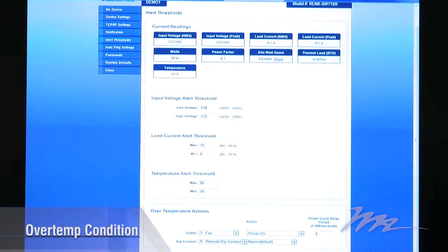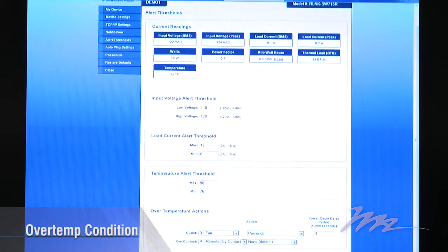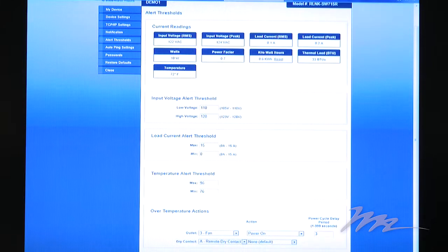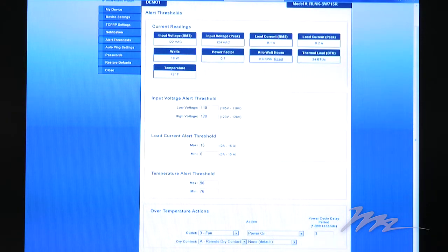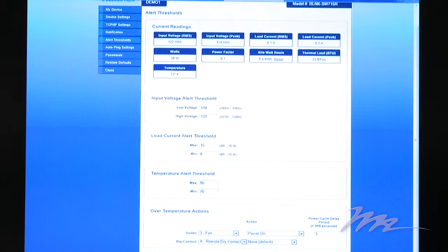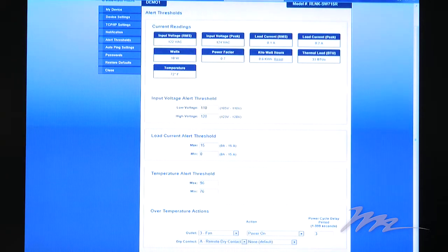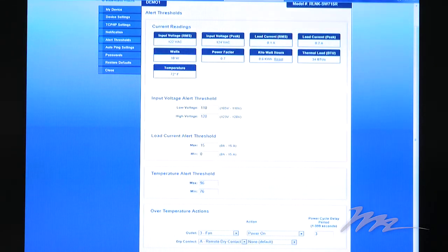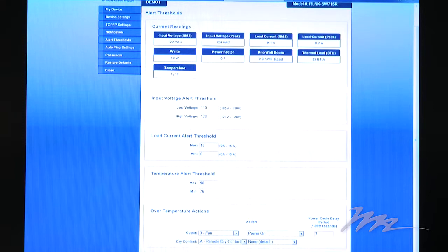If RackLink detects an over-temperature condition, it has an additional trick up its sleeve. The integrator can optionally choose to have RackLink automatically shut down connected equipment or power up additional cooling devices to protect the system from damage. In addition, RackLink will send out a notification email to the integrator to alert him of the over-temperature condition.